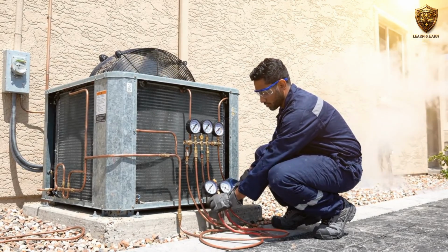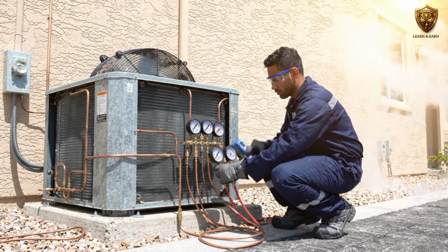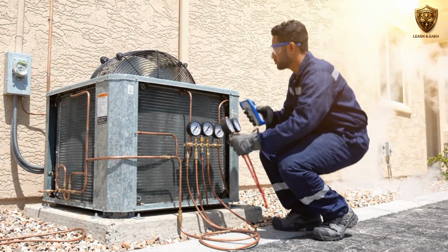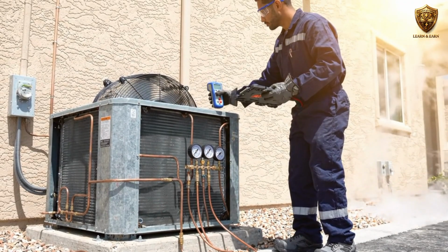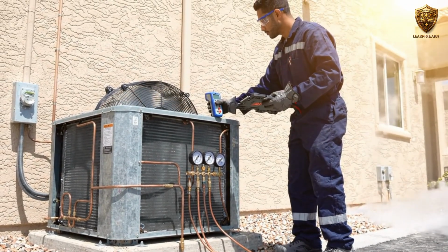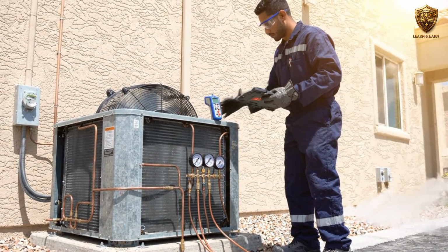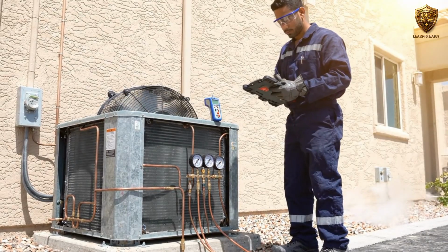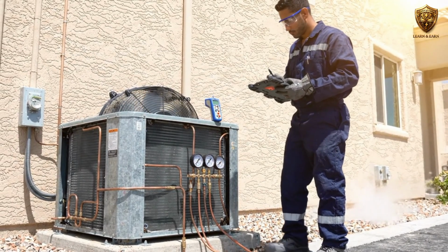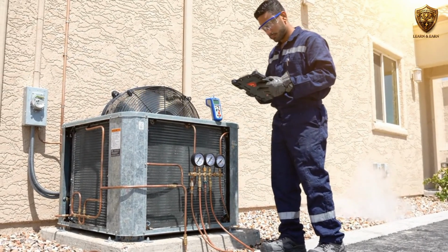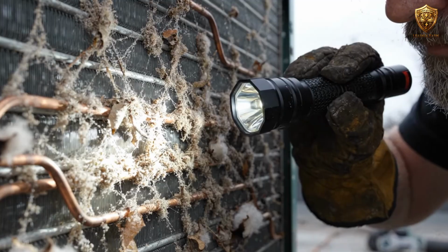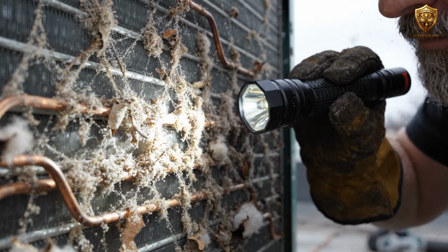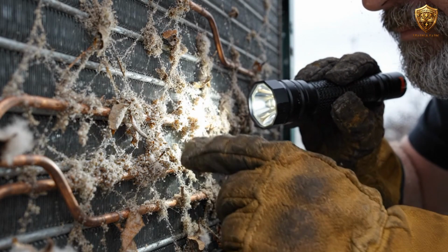Condenser performance is another area that can create serious cooling problems, especially in hot climates. The outdoor condenser has to reject heat into the surrounding air. If the condenser coil is heavily blocked with dirt, dust, or debris, heat transfer becomes more difficult. The system may run at higher operating pressure and the compressor can work harder. In very hot weather, this problem can become more noticeable because the outdoor air is already warm.